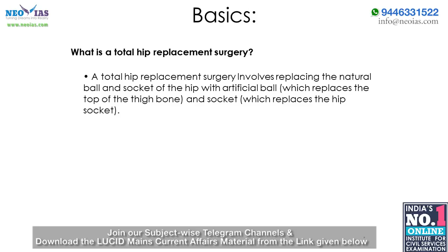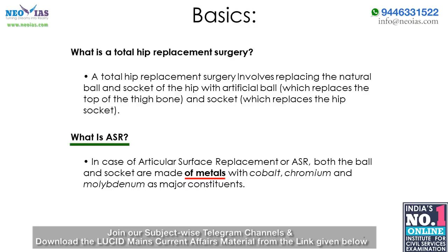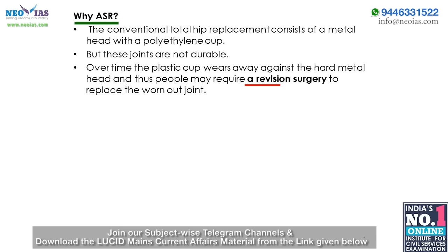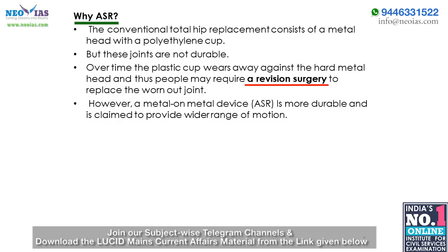Next we can see what is ASR. In case of articular surface replacement or ASR, both the ball and socket are made up of metal with cobalt, chromium and molybdenum as major constituents. Why ASR? The conventional total hip replacement consists of a metal head with a polyethylene cup, but these joints are not durable. Over time, the plastic cup wears away against the hard metal head, and thus people may require a revision surgery to replace the worn out joint. However, a metal-on-metal device, that is ASR, is more durable and is claimed to provide a wider range of motion.